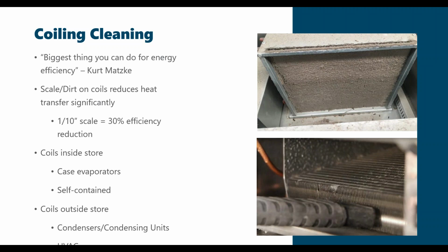When we're talking about coil cleaning, coils inside the store are case evaporators, which also have health benefits, which I'll get into. Self-contained units: Nicole mentioned those self-contained units are dumping a lot of heat onto the sales floor. If there's grime and dirt and anything that they pick up on the sales floor on those condenser coils, it's so much more difficult for that heat to be rejected than if it was a nice clean coil. And so that's added inefficiency, added waste heat that is going out onto the sales floor and then has to be handled by the HVAC system.